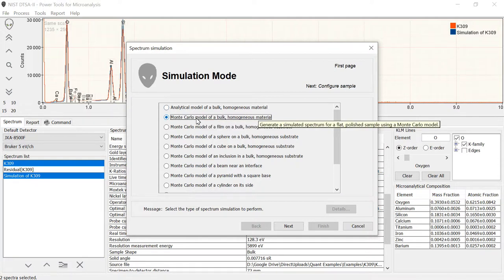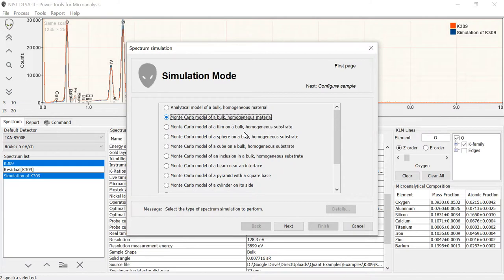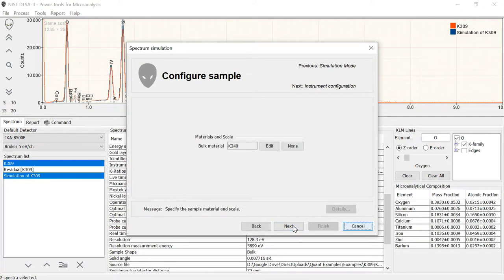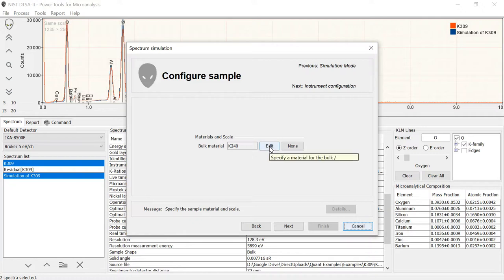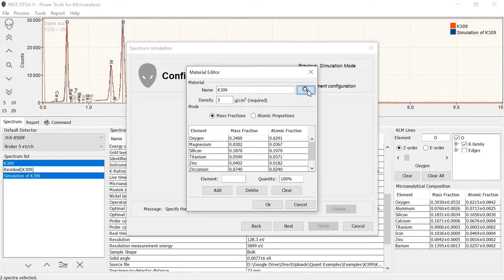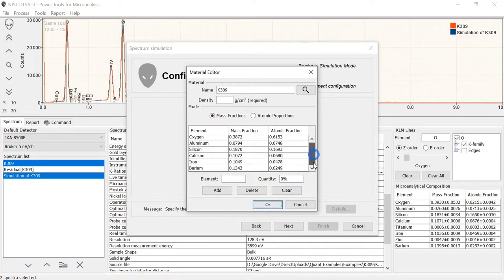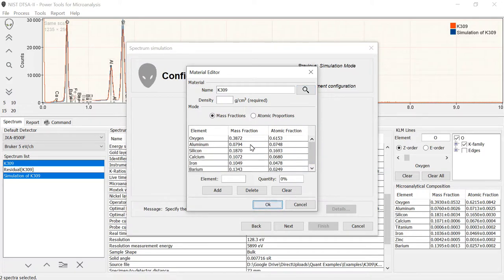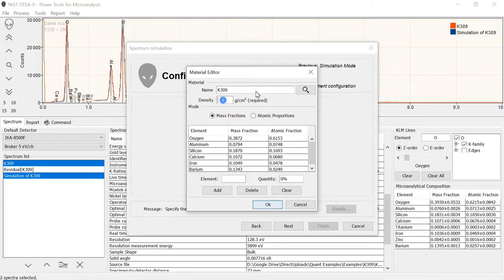In this example I'm going to do a Monte Carlo model of a bulk homogeneous material just like the material from which this spectrum was collected. I'm going to go ahead and simulate the same spectrum again. So we're going to go with K309. To do that we're going to use the material editor to enter in the material. This material happens to already be in the database so the composition for it is already present. So fortunately we don't need to enter this information again which makes it good for an example like this.